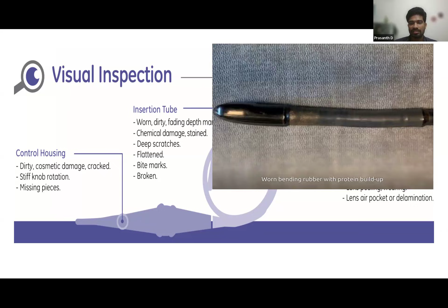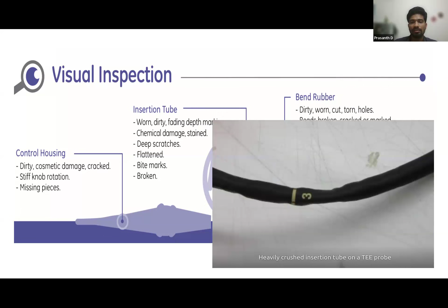And sometimes heavily crushed flexible shaft can be present. So you have to check each of the parts of the TEE probe after removal of the TEE probe. Some examples of TEE probe damage: unapproved disinfectant use, not suggested by the manufacturer, will cause a cracked proximal bead. Here, because of improper cleaning, human protein buildup in the peripheral areas of the lens tip. And in the third image, we can see in the upper part, some silicon beading is removed from the lens.